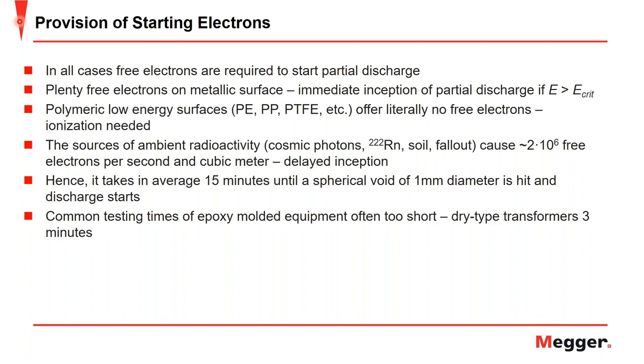And we talked about ionization through the photons hitting a gas molecule. These sources of the ambient radioactivity can cause, statistically speaking, roughly 2 times 10 to the 6th free electrons per second in a cubic meter. This results in delayed inception. So if not triggered artificially, statistically speaking, it takes on average 15 minutes until a spherical void of 1 millimeter in diameter is hit, and therefore discharge starts.